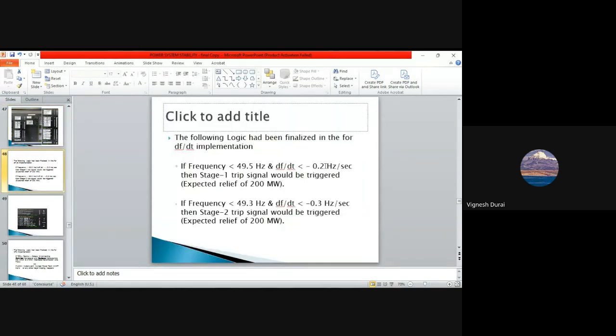Next we have df by dt. If your frequency is below 49.5 and at the same time your frequency is drastically changing, then again stage 1 will be triggered. Next, suppose your frequency is immediately dropping to 49.3, then stage 1 and stage 2 both will be triggered. It won't get delayed. At the same time, your under frequency trip will also initiate. These all things will happen automatically. We have trip signals for that in SCADA, so that if it reaches the permissible limit, it will automatically trigger the tripping.